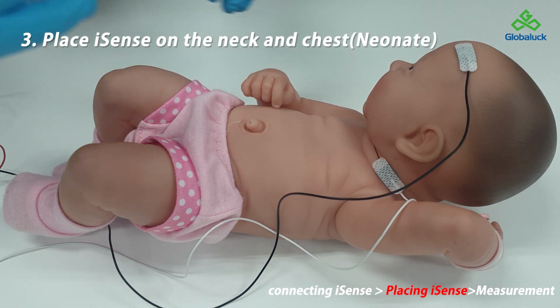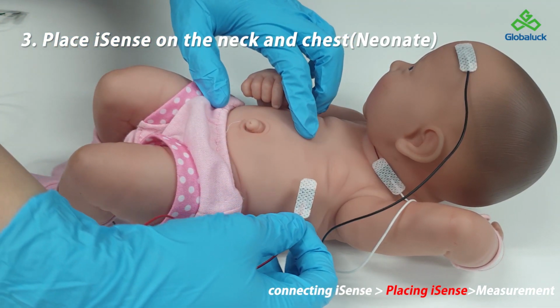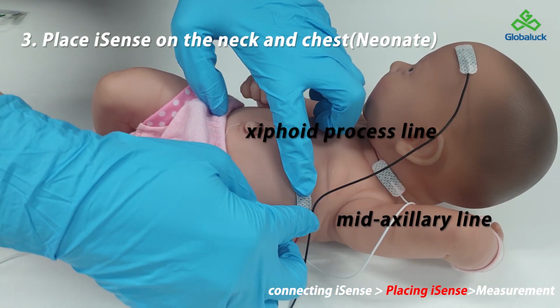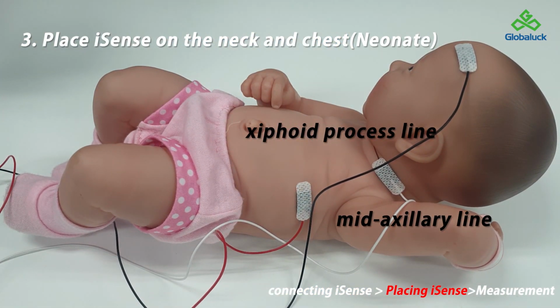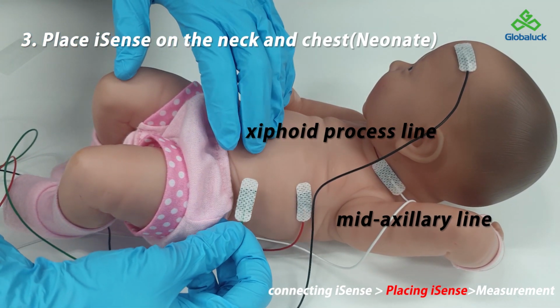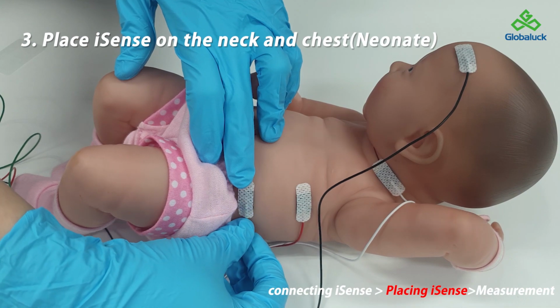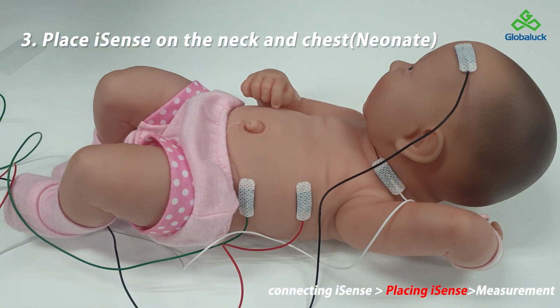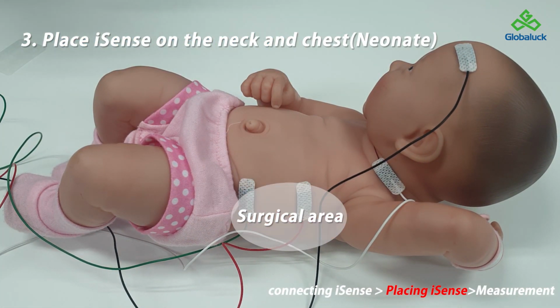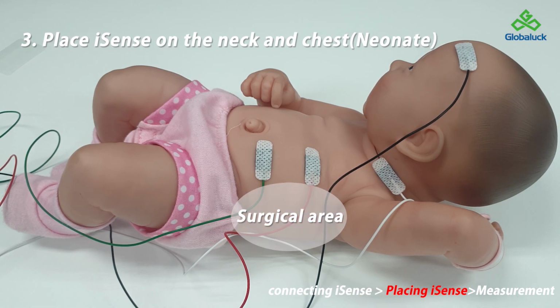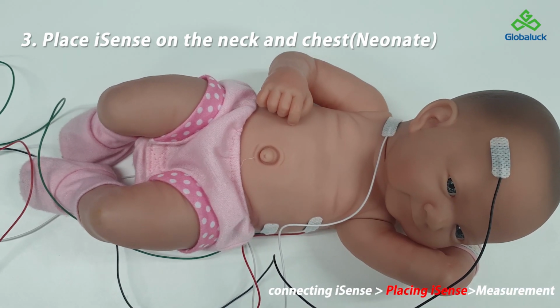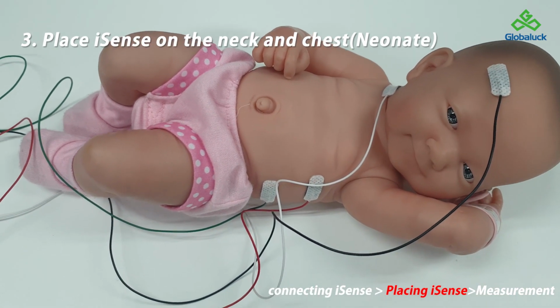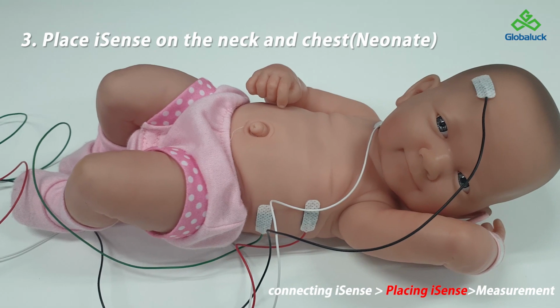The sensor C is placed on the mid-axillary line at the xiphoid process level. The sensor D is placed about 5 to 20 centimeters below the sensor C. In the case of neonate patients, the sensor D can be placed at the left thigh. In case of surgical patients, place sensors at the level of the xiphoid as far as possible from the surgical area. The sensors A and B can be moved from the left to the right if you cannot attach them on the left.